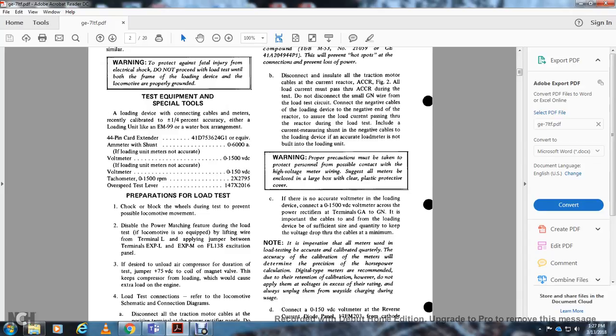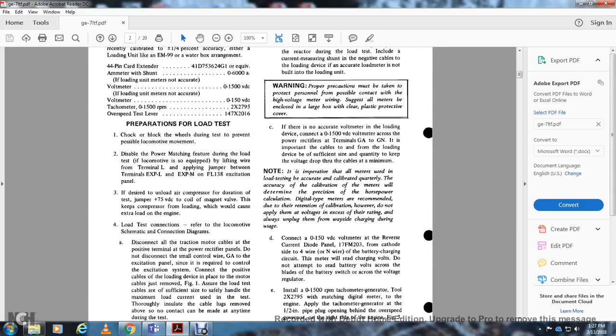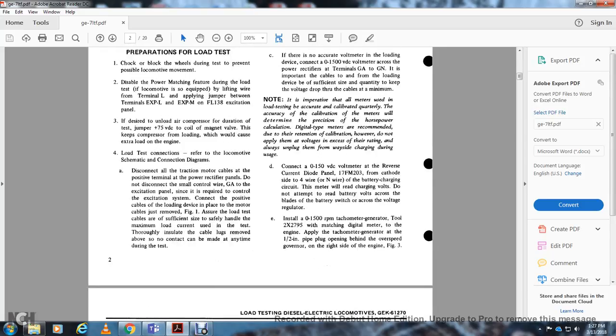If there is no accurate voltmeter with the loading device, connect a 0 to 1500 volt DC voltmeter and ammeter across the rectifier terminals GA to GN. It is important that the cables to and from the loading device be of sufficient size to keep the voltage drop through the cable to a minimum. Notice: it is imperative that all meters used in load tests are accurate, calibrated quarterly. Accuracy of the meter calibration determines the precision of the horsepower calculation.